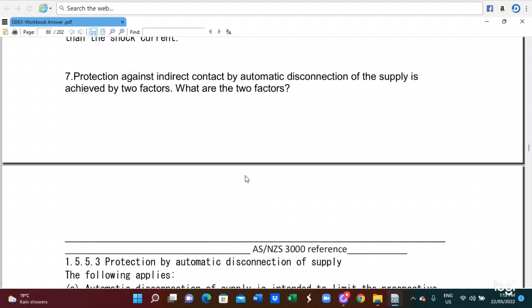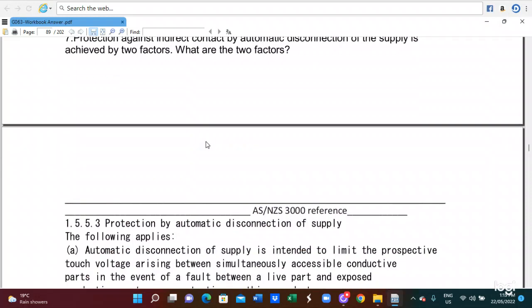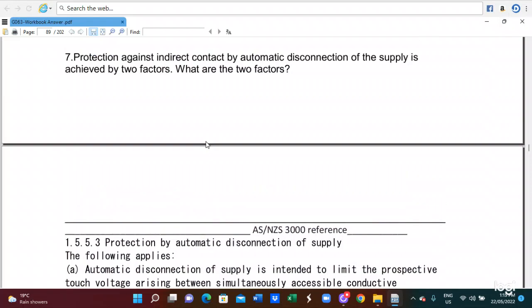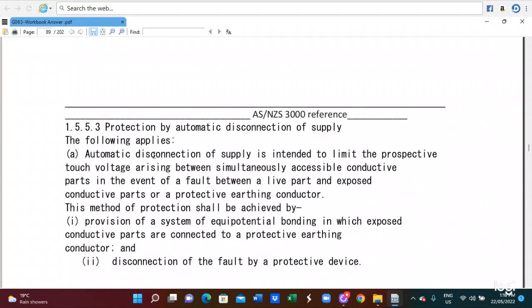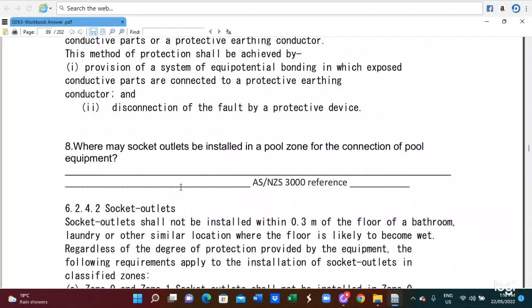Protection against indirect contact by the automatic disconnection of supply is achieved by two factors. What are these two factors? So this is 1.5.5.3. In this case, automatic disconnection of supply is intended to limit the prospective touch voltage arising between simultaneously accessible conductive parts in the event of a fault between the live part and the exposed conductive part or the protective earthing conductor.